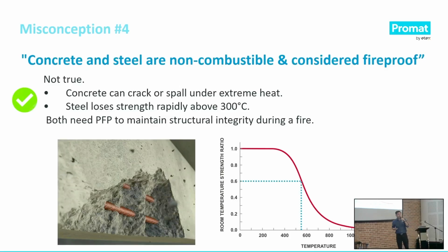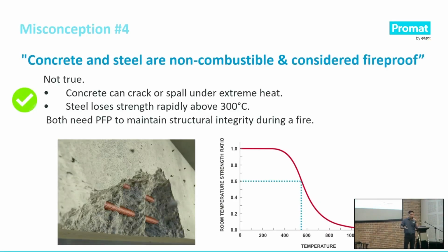For concrete itself, when you lay it—we do a lot of tunnel projects, unfortunately not so much in Malaysia, but in Europe we have many tunnel projects dealing with a lot of concrete—it is recognized that concrete will start to spall during fire time. The moisture trapped inside the concrete, once it reaches a certain boiling point during fire, will cause it to spall and expose the reinforcement bar. That's where the reinforcement bar starts to lose strength and begins to deflect and deform, and eventually the whole structure starts to collapse.